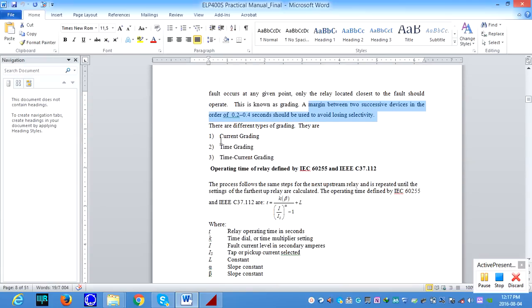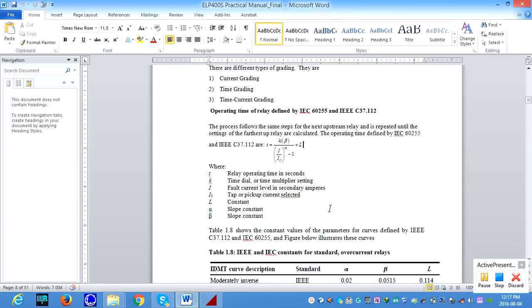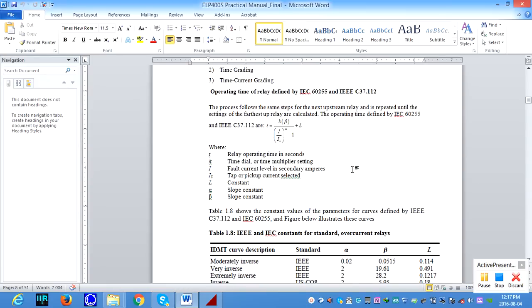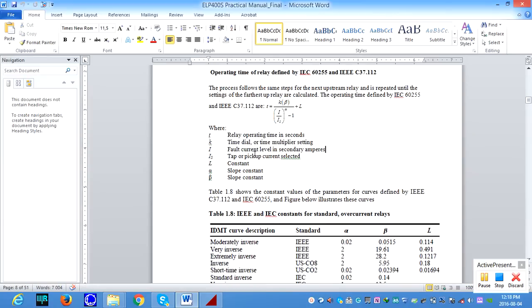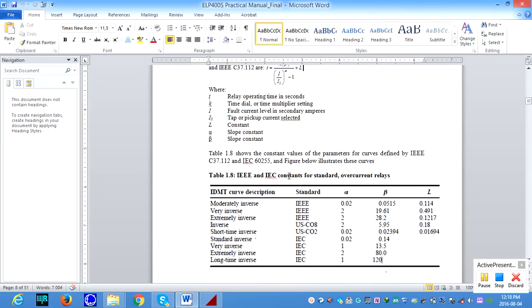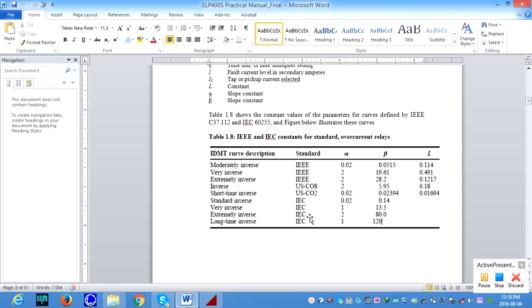There are different types of grading: current grading and time current grading. And the next important thing, the operating time of the relay is specified according to the IEC standard or the IEEE standard. According to the IEC and IEEE standards, the operating time is described as T, which is mathematically given in this equation. The notations of these symbols will be described here. And also the operating time of the relay will change according to the characteristic curve. For example, you can see there are different characteristic curves.